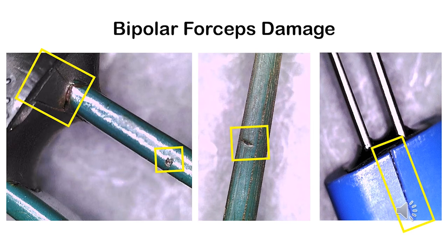The picture in the middle is a cut from probably another instrument from staging, and you can see lines going up and down the insulation, probably from a metal brush. The picture on the right is that base, which is again the weakest part of an insulated forceps, but in this case it's the base that split all the way down, which can harbor debris.